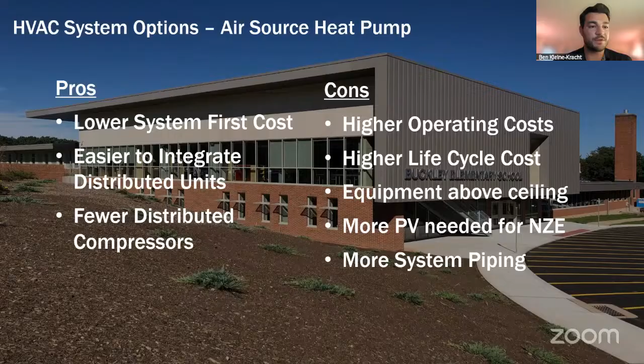Yeah, so we'll just run through some of the pros and cons for each one of these options. Again, air source heat pump is probably the worst performing. It would be kind of a stretch to try to get to zero with this one, but it can be done with canopies if that's what you guys are comfortable with. It has a lower first cost, but we'll walk through the life cycle over the course of this presentation. And then with the big units, we don't have that problem fitting distributed units into classrooms. All the compressors are in one location, so you're not running from one wing to another to look at that. But again, it's higher life cycle costs, more system piping, and the other things we mentioned.